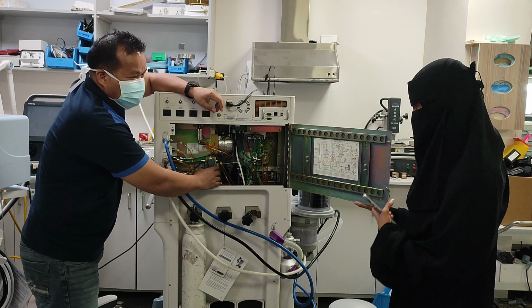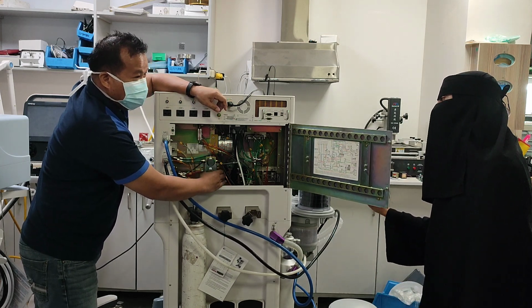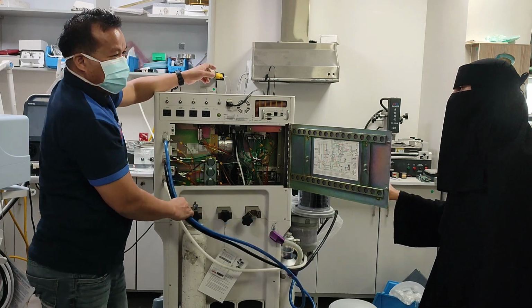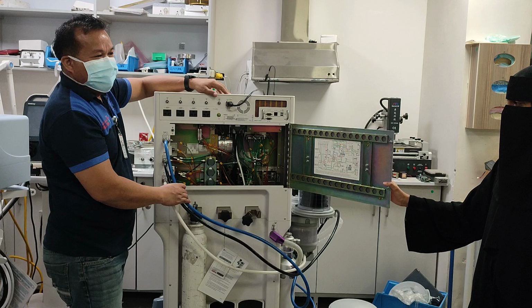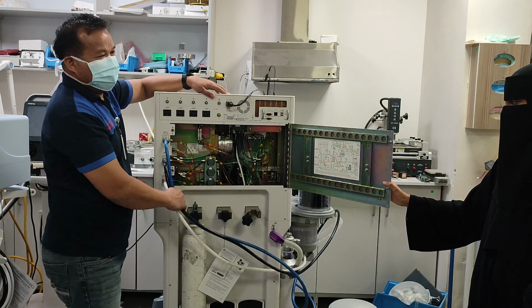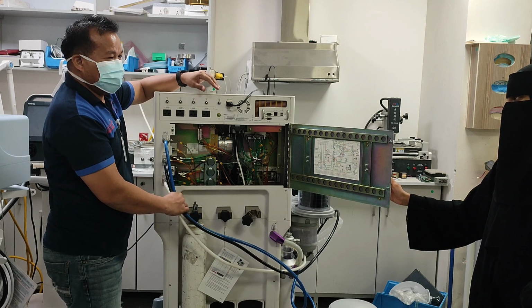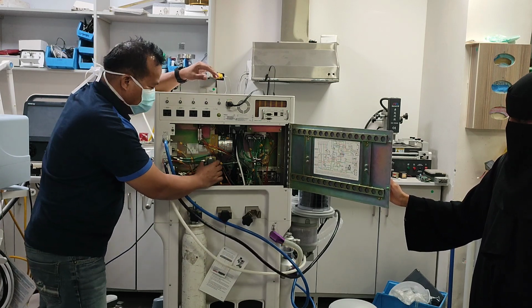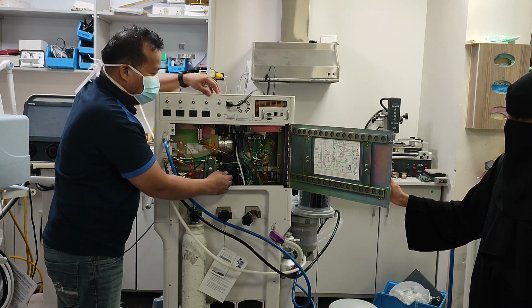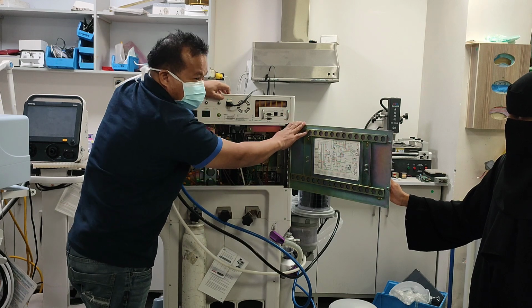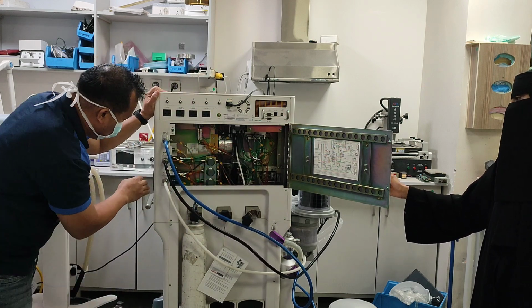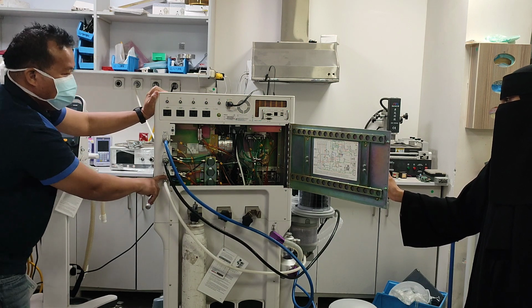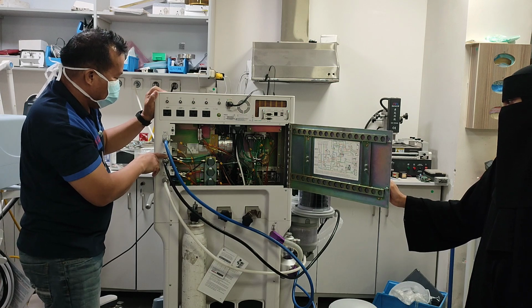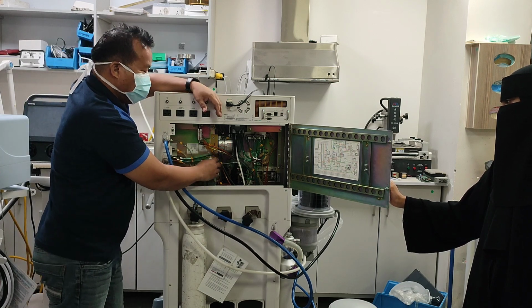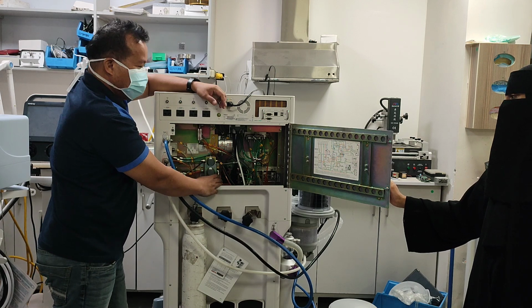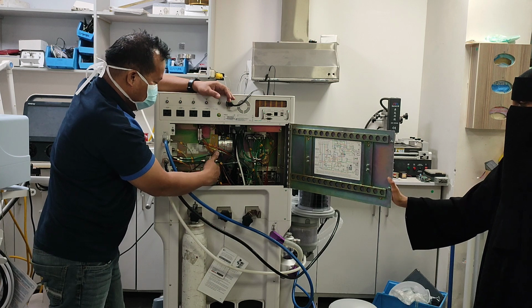So there is a regulator here. What is the purpose of the regulator? Our supply gas is high pressure. There are 2 types of supply gases: high pressure and low pressure, meaning low pressure is already regulated. So why do we have a regulator here? The requirement of the gases here is 40 to 60 psi. If you see here, this one is 40 to 87 psi, and this one is also 40 to 87 psi. That's why there is a regulator here. The purpose is to regulate the pressure to what is required.